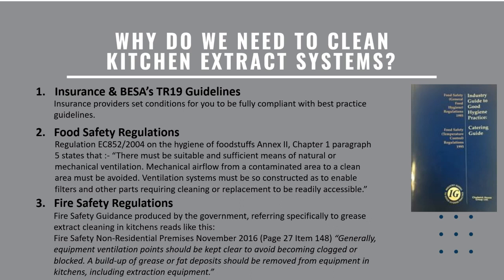So why do we need to clean kitchen extract systems? Most people know why. It's a fire hazard. And although to date, as far as I know, no one has died due to a commercial kitchen fire, that is by far the most compelling reason to address a known and very real fire risk. Insurance companies also require evidence that cleaning has taken place and that grease buildup is being removed by a third-party contractor, especially in the event of a fire and a potential claim.